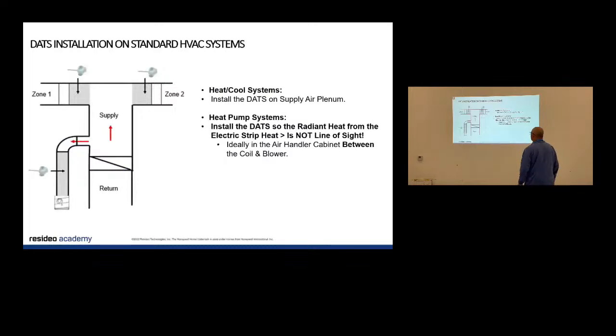The other thing we need to do is install some sensors when you're using zoning. Because as I close dampers and open dampers, we all know that the heat exchanger in your furnace can only take so much heat. Or if you have an air conditioner and you don't have the right airflow across it, you're going to freeze up that coil. So we put sensors in our kits, and all the contractor needs to do is read the directions, which I know sometimes is a challenge. And they have to put the sensors in the right space.